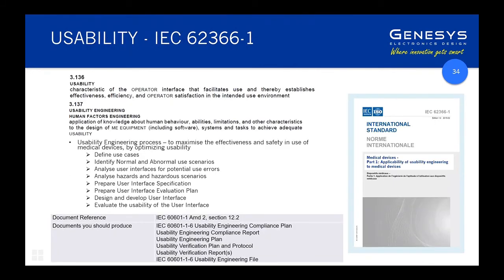IEC 62366 for usability is a whole separate topic — we've had a webinar on this. The headline standard that calls this up is 60601-1, which calls up 60601-1-6, which in turn calls up 62366-1. I won't go into this in detail today but refer to the webinar recordings for more information on dealing with usability engineering.